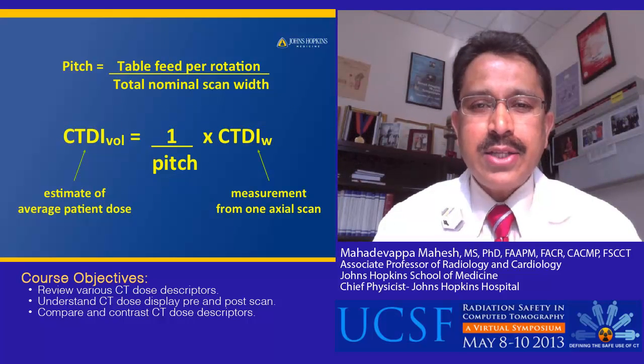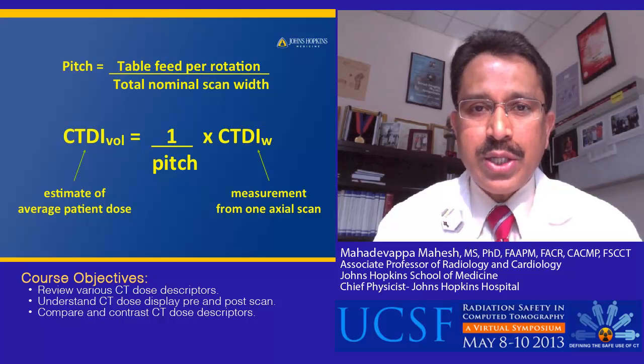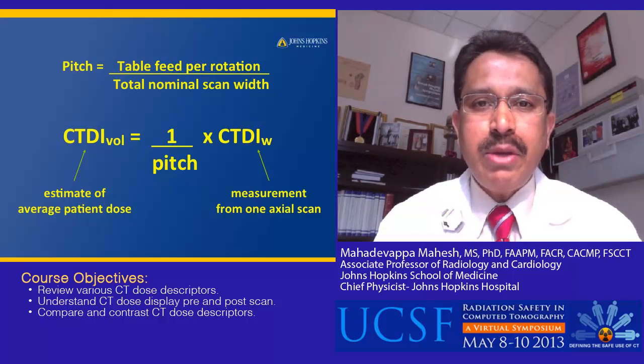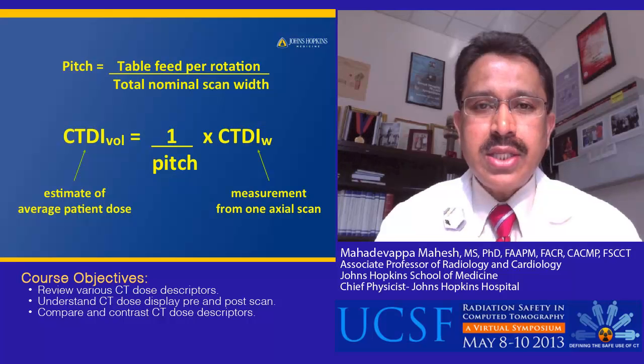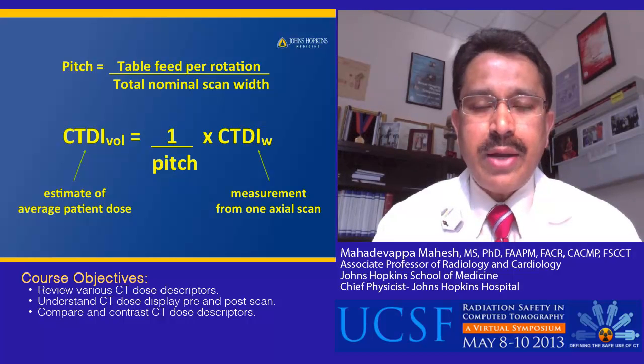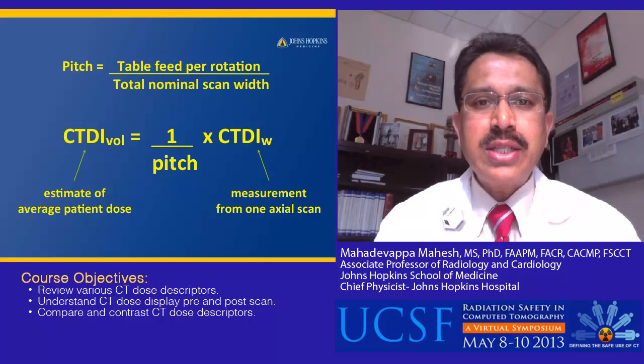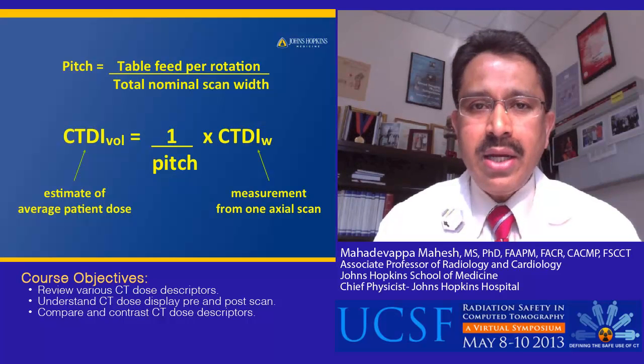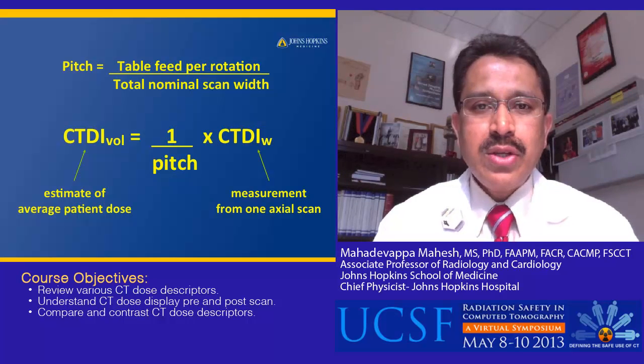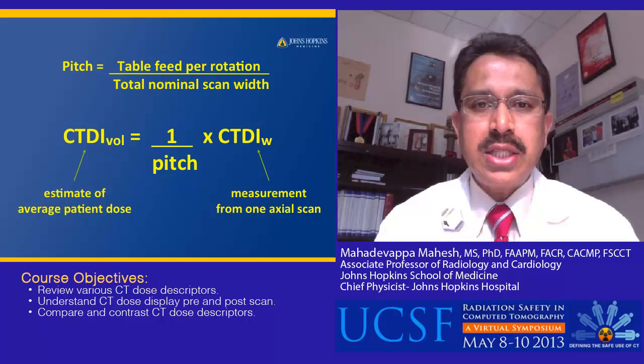Pitch is defined as the ratio of the CT table travel per gantry rotation divided by the total beam width. The radiation dose in a CT scan is inversely proportional to the pitch value. If the pitch value is very small, the radiation dose is higher. If the pitch value is very high, the radiation dose is lower. So there is an inverse relationship between pitch and the CTDIvol.